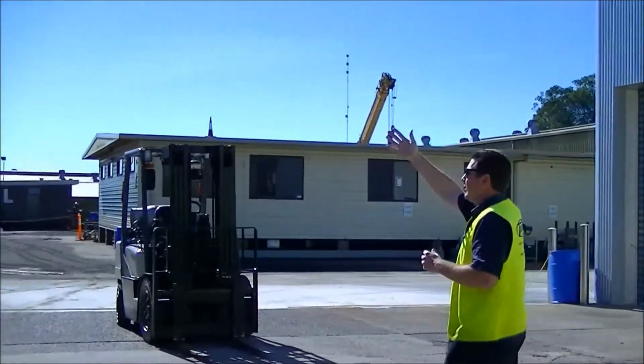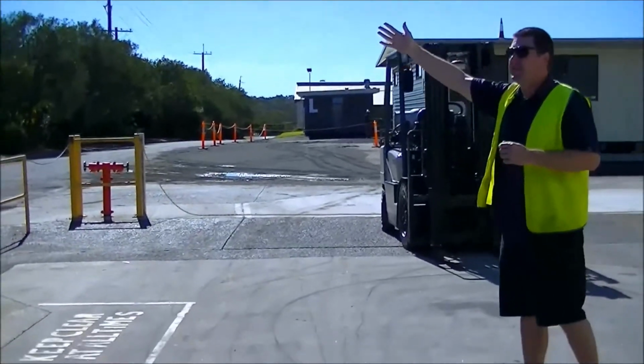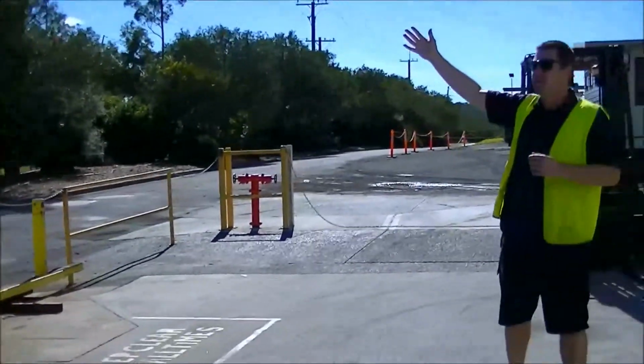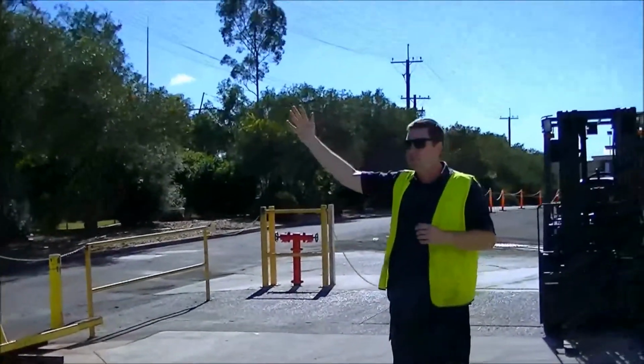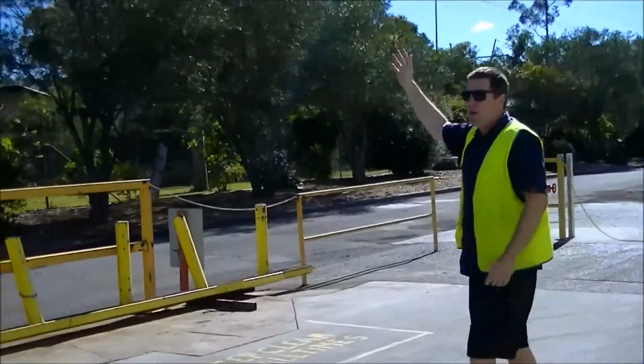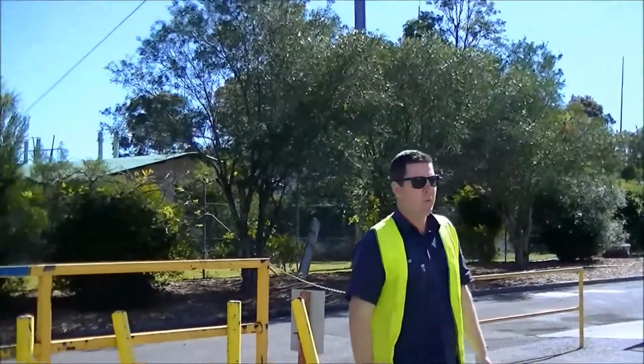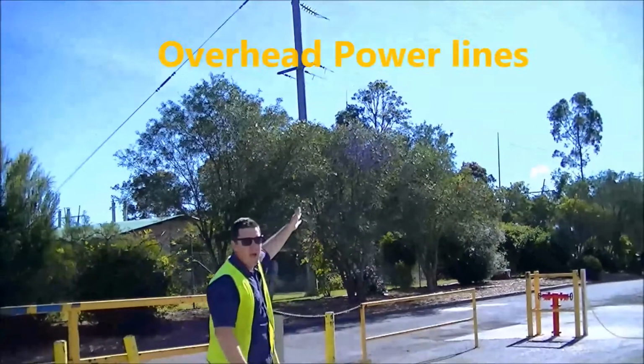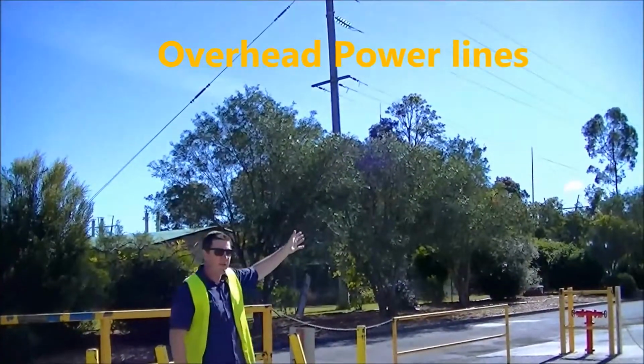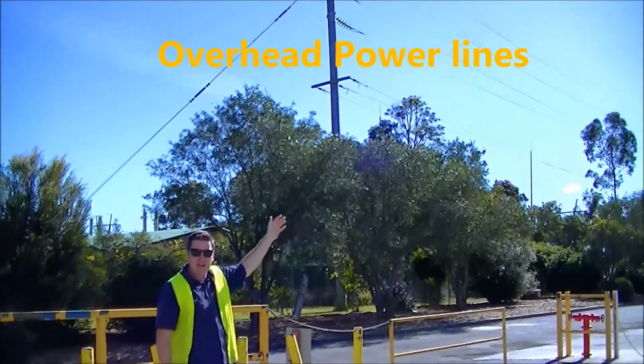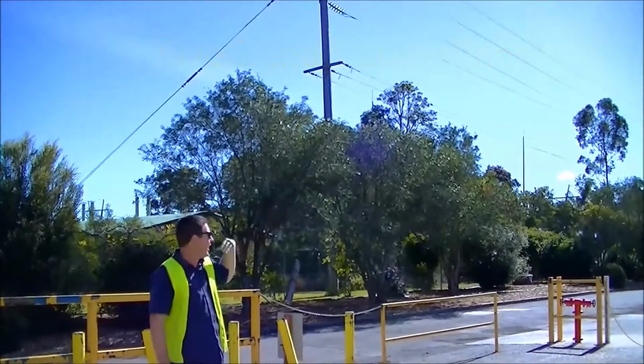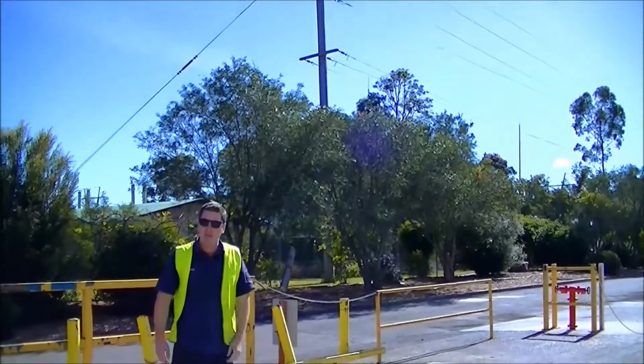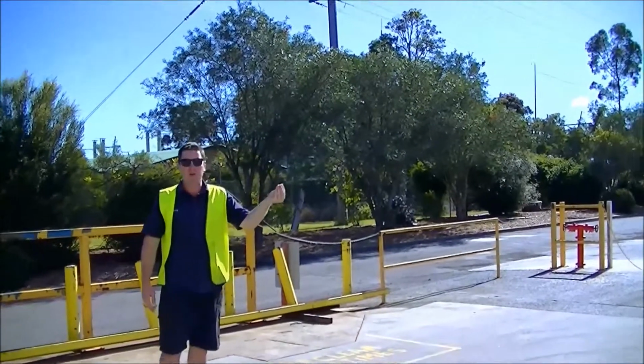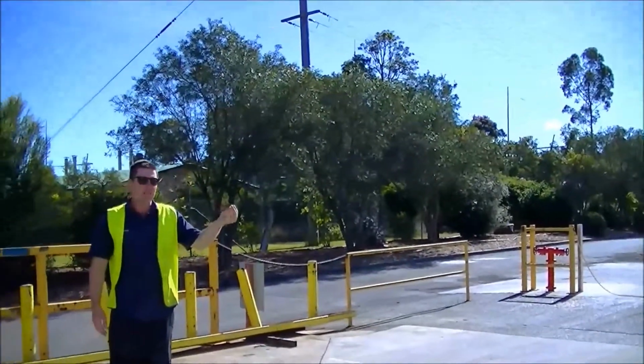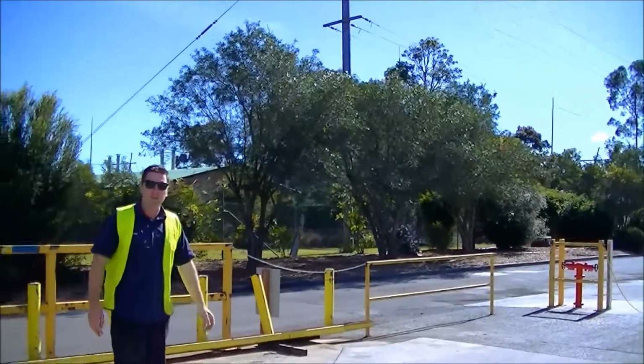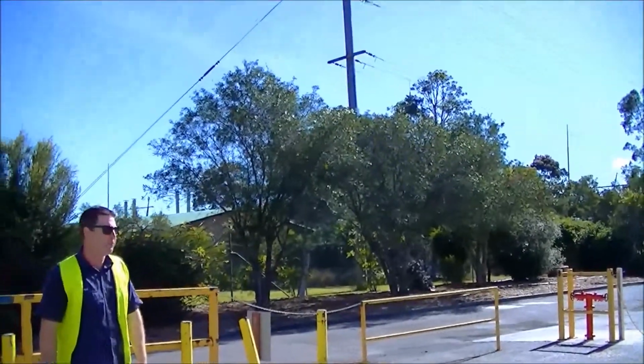Off to the side, we can see we've got some trees. Again, we need to be aware of any trees that are in our working area. Keep a safe distance away from them. One of the major hazards we need to be aware of is our overhead power lines. Make sure you maintain your safe approach distances as per your state regulation. If I wasn't sure of what the voltages were in that, I'd speak to the local power authority to get the voltage, and then I can apply the relevant distances for that.